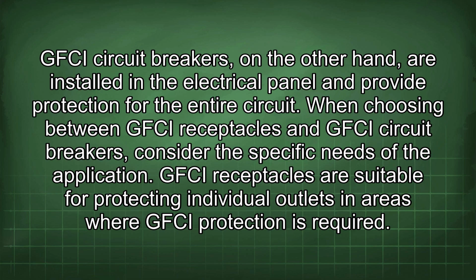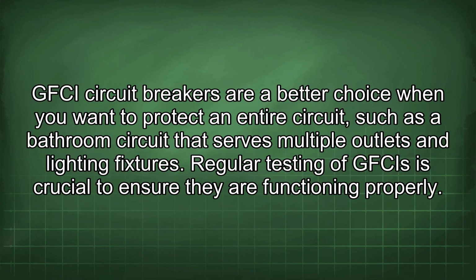When choosing between GFCI receptacles and GFCI circuit breakers, consider the specific needs of the application. GFCI receptacles are suitable for protecting individual outlets in areas where GFCI protection is required. GFCI circuit breakers are a better choice when you want to protect an entire circuit, such as a bathroom circuit that serves multiple outlets and lighting fixtures.